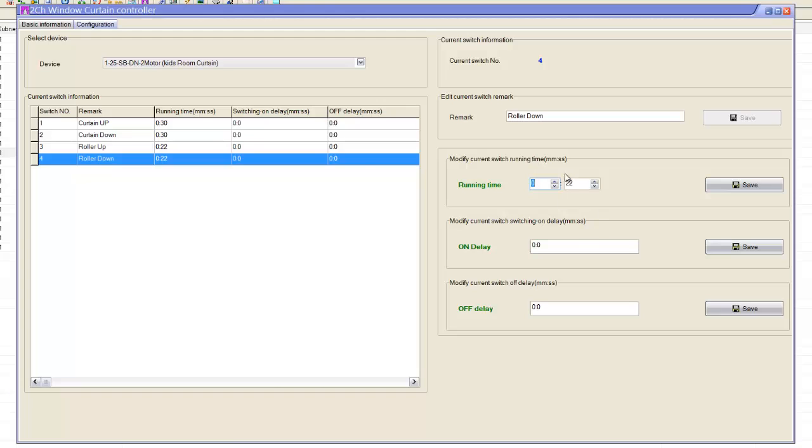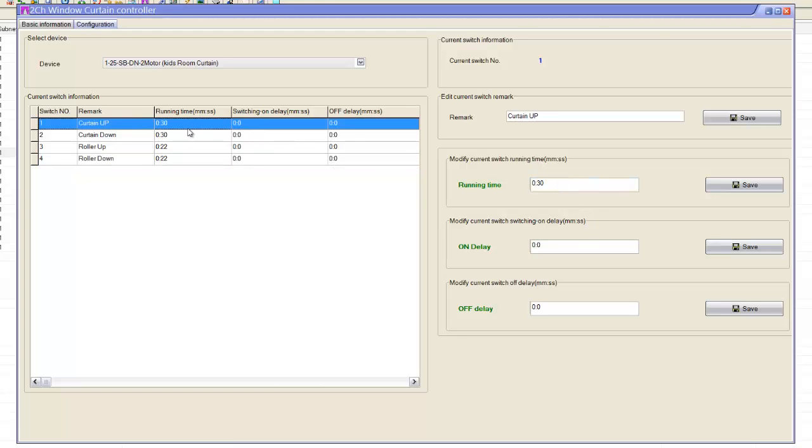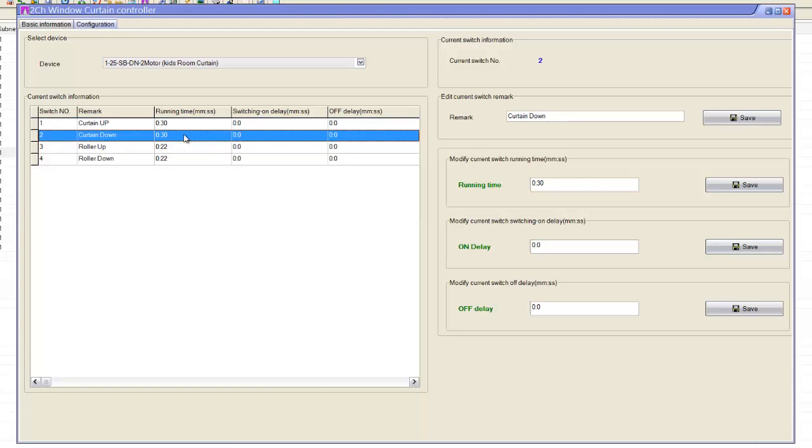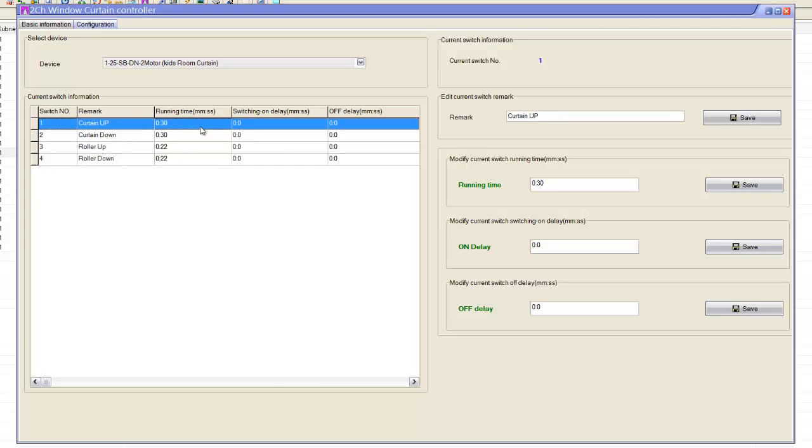Let's see I have this motor take 30 seconds to go up and 30 seconds to go down, or to open and close. So first of all, I have to configure each channel. Like this channel, the switch running time, it's 30 seconds. When I press up, it takes 30 seconds and goes off to stop the motor.